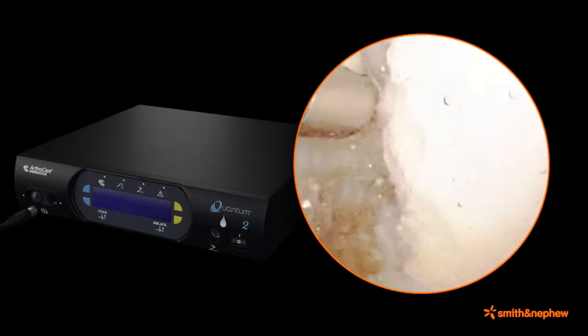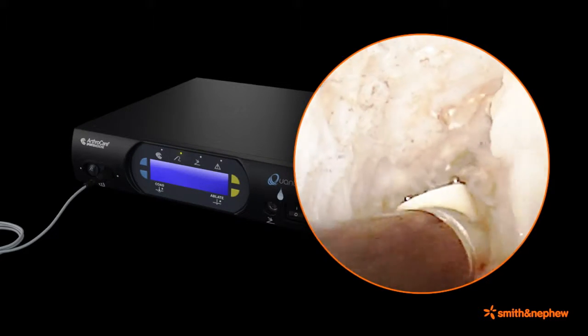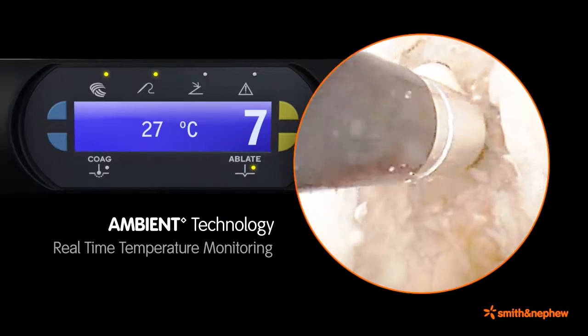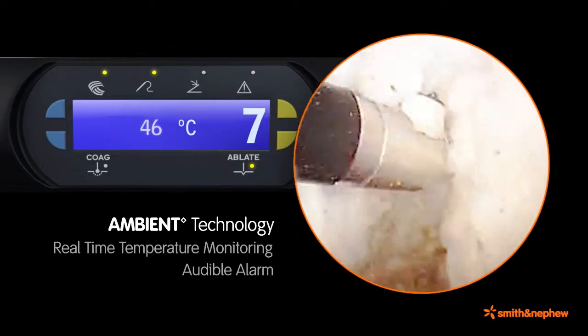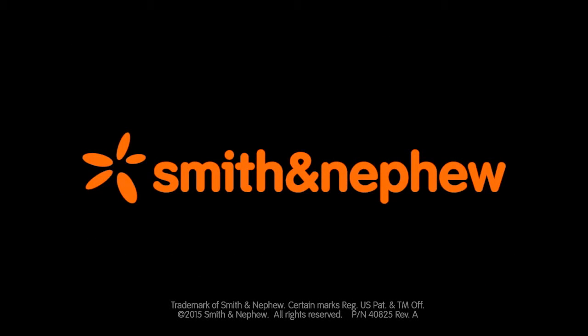Coblation technology has been well adapted for soft tissue ablation. In addition, select coblation wands include AMBIENT Technology, which provides accurate real-time temperature monitoring of the intra-articular fluid and provides an audible alarm when the temperature exceeds the user-selected temperature set point.